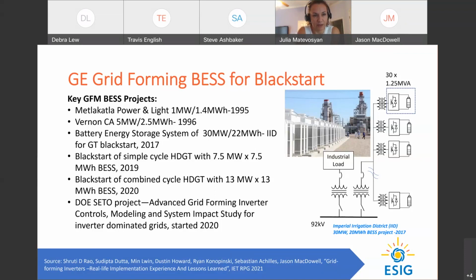Addition of these batteries didn't require large changes to the existing plant, it was only about implementing the battery and appropriate controls. Soft start is used for a grid forming battery to avoid large inrush currents at motor energization and transformer energization. One thing I wanted to mention, GE together with NREL, First Solar, and a number of other academic and industrial partners are participating in a DOE-funded project on advanced grid forming inverter controls, modeling, and system impact study for inverter-dominated grids. This project looks at development of grid scale grid forming inverter controls, and plans to conduct studies on large scale systems to see how grid forming inverters impact the grid.